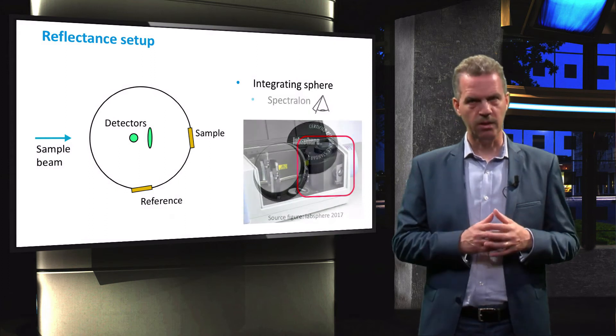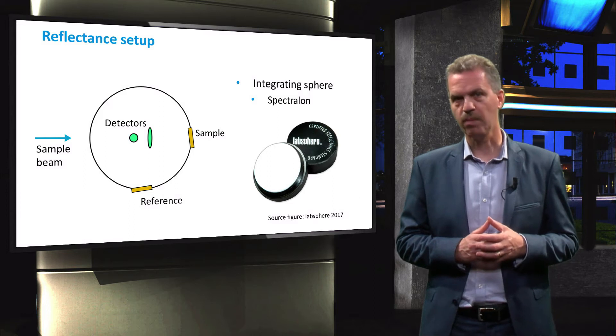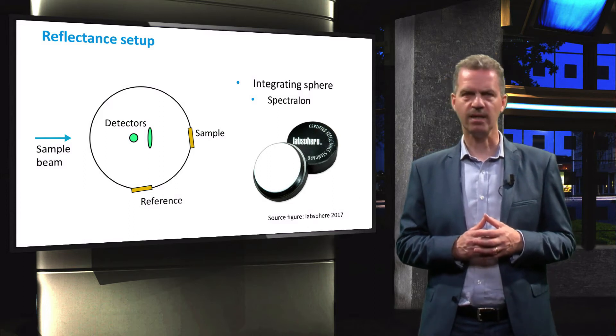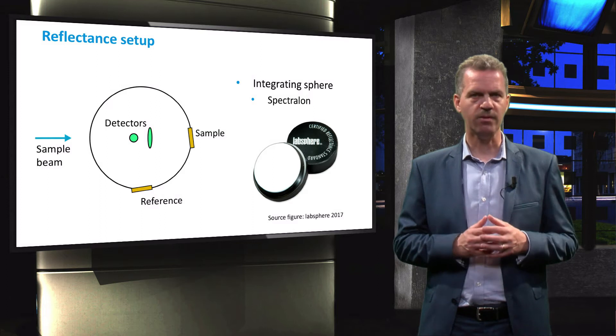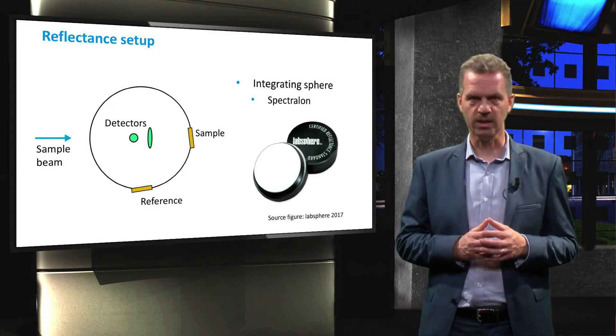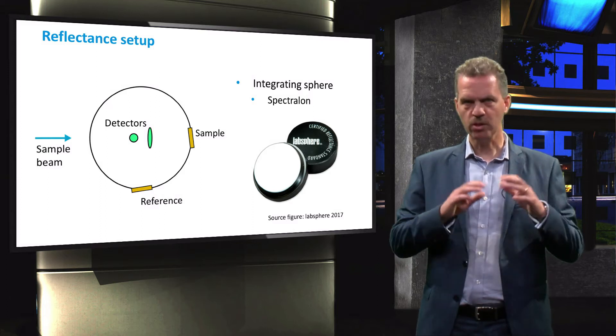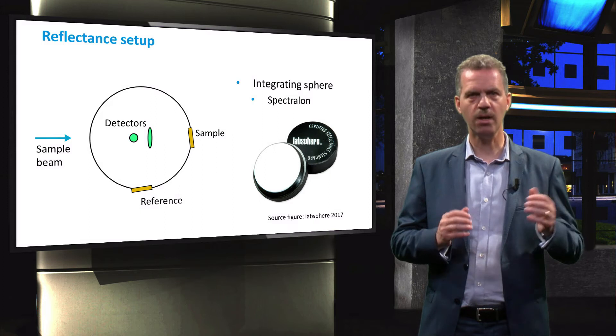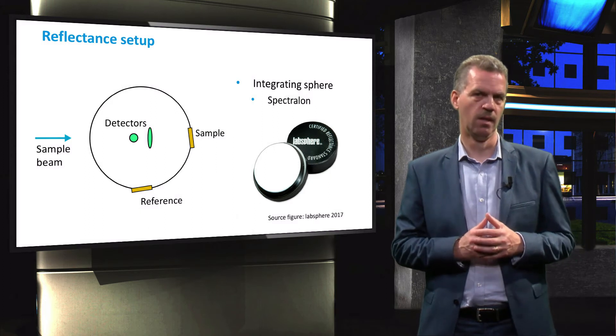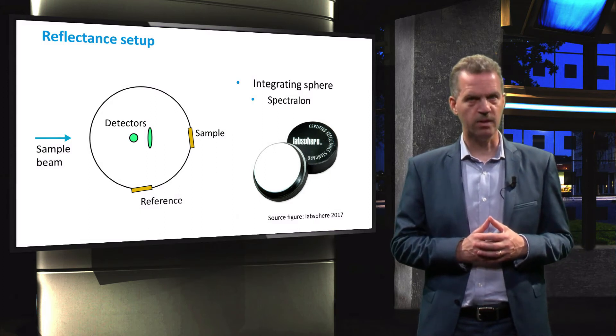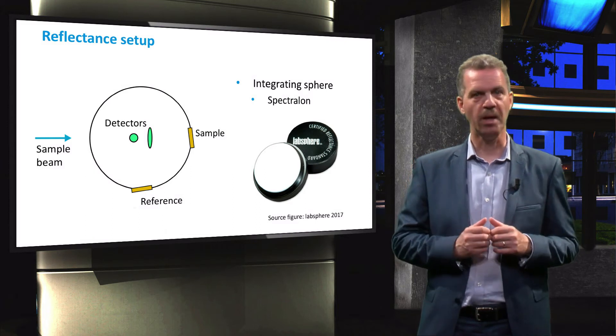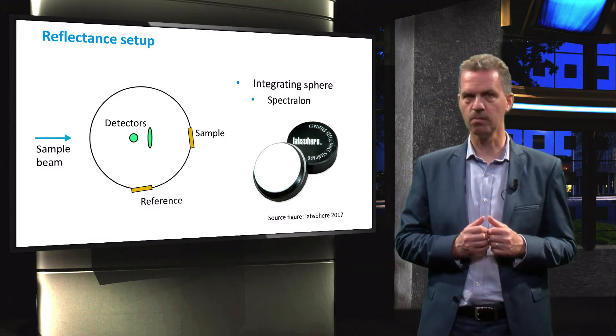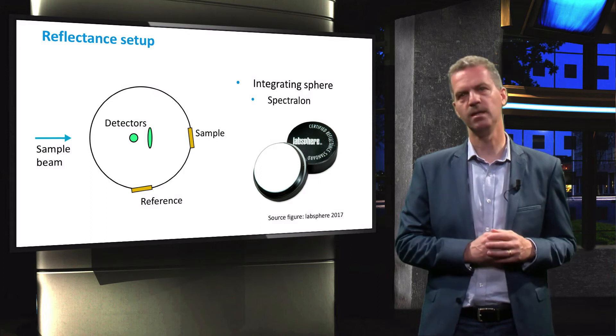The interior of this sphere is coated with spectralon, which is a highly scattering and reflective material. If light enters the integrating sphere, it will reflect multiple times and scatter in all directions. The electromagnetic field will therefore be homogeneous inside the sphere, making it possible to evaluate the smallest light intensities at a single point in the sphere.